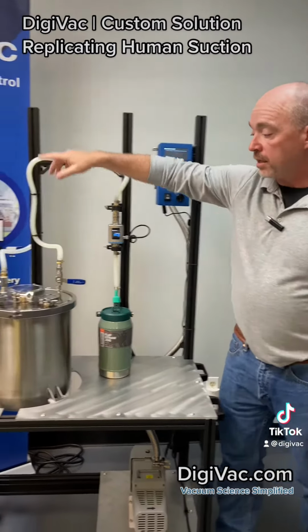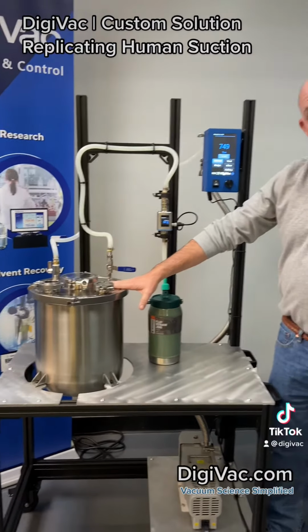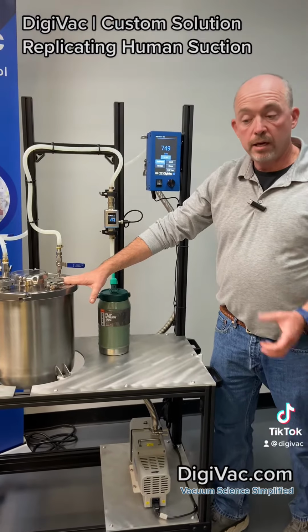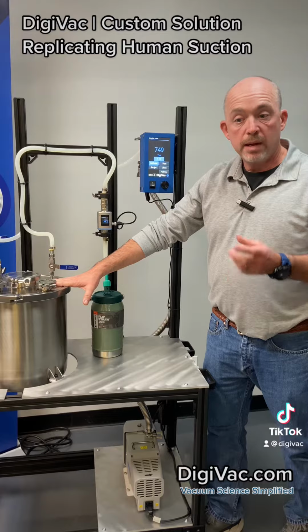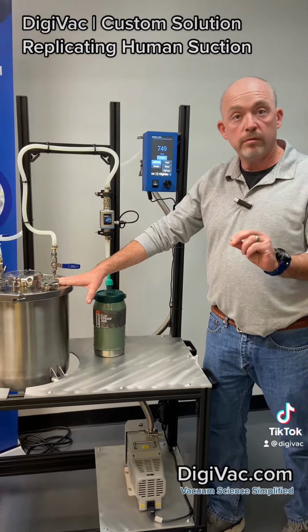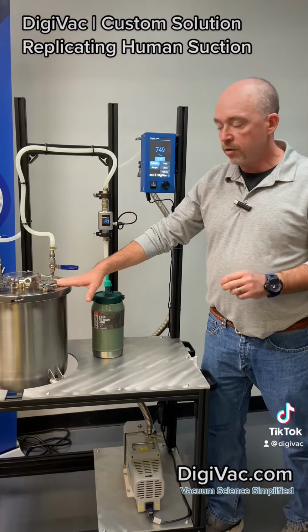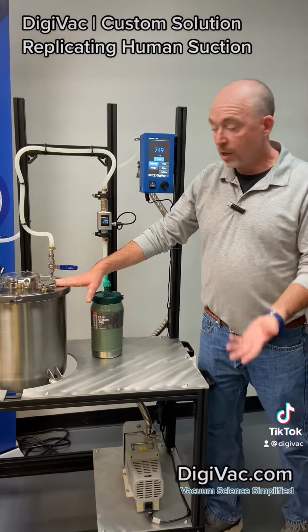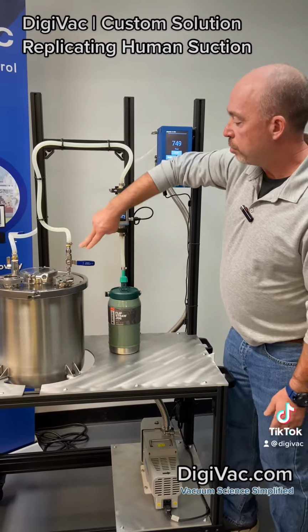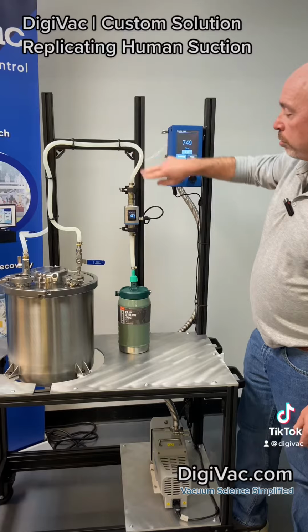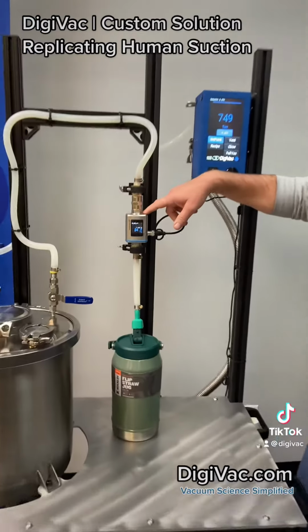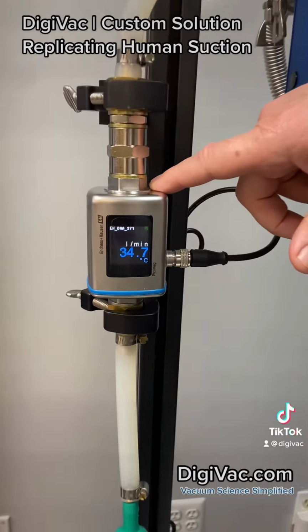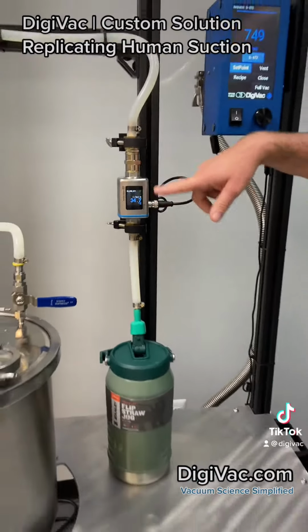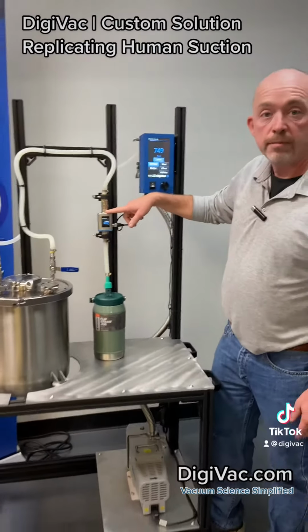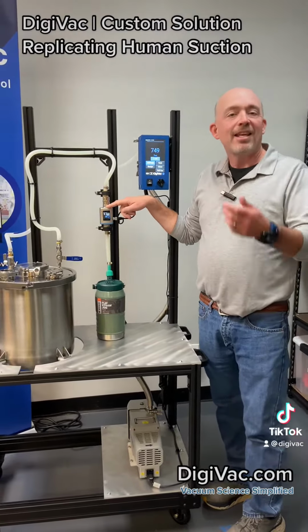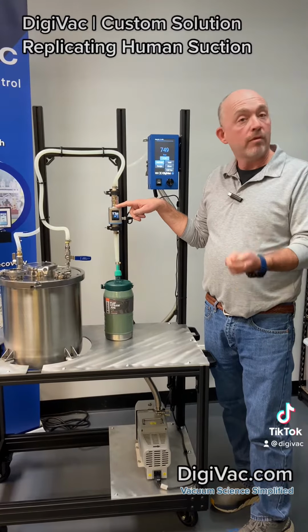That's then connected to this chamber here, which is basically a ballast chamber, so we can maintain a specific vacuum level despite suction over time, and it also acts as a repository for water so we can drain it out. Then we actually flow through a water flow sensor. So this water flow sensor is telling us how much water is actually flowing at any particular time. And as you might gather, the greater the suction, the more the flow.